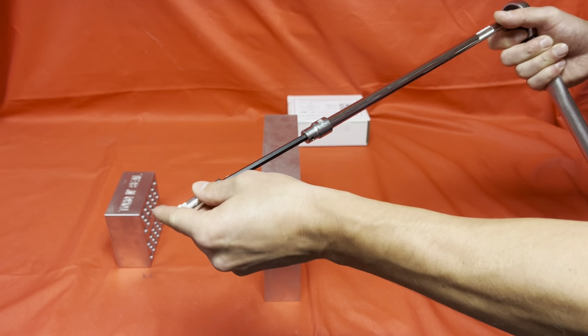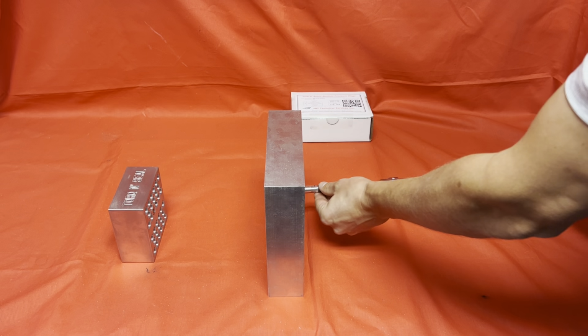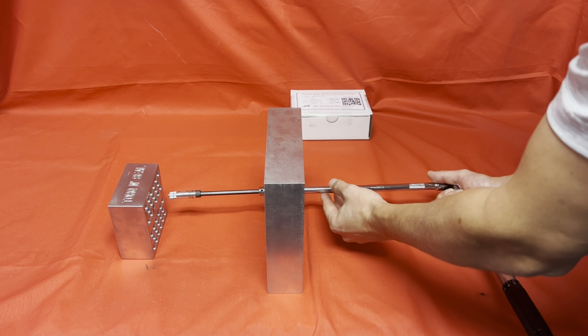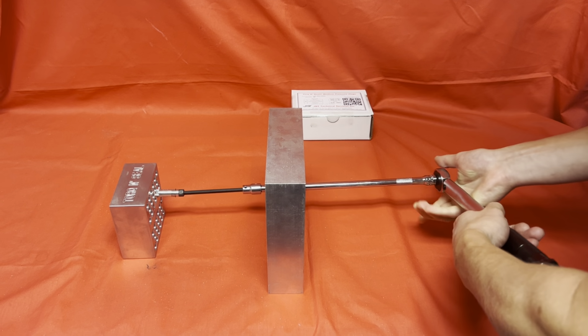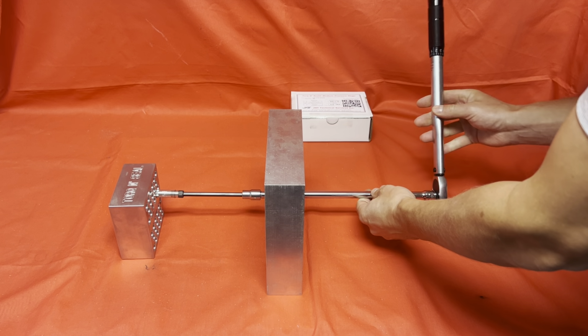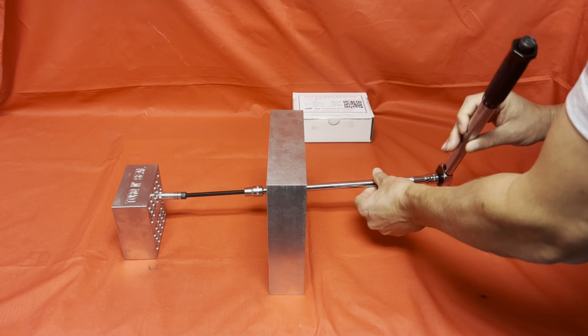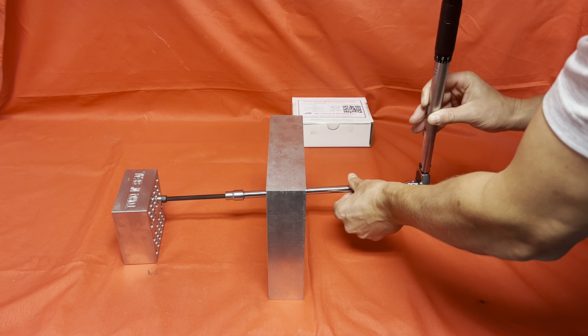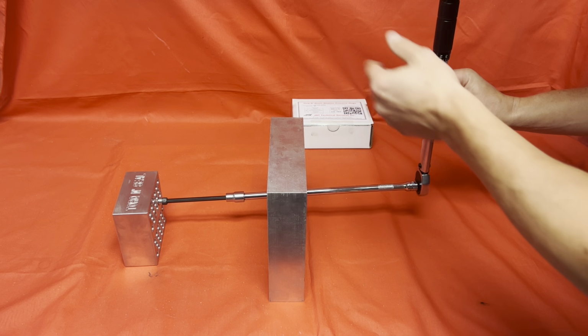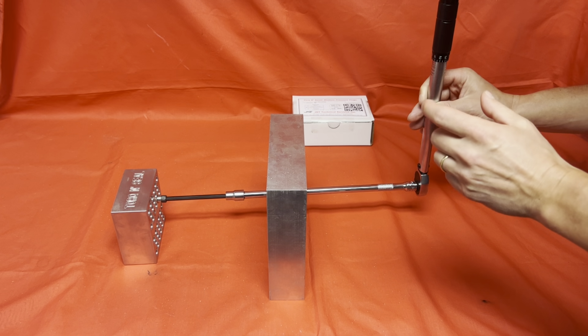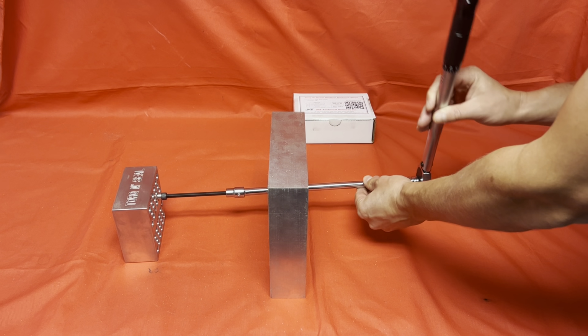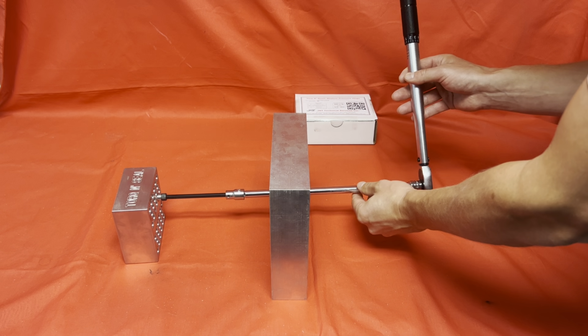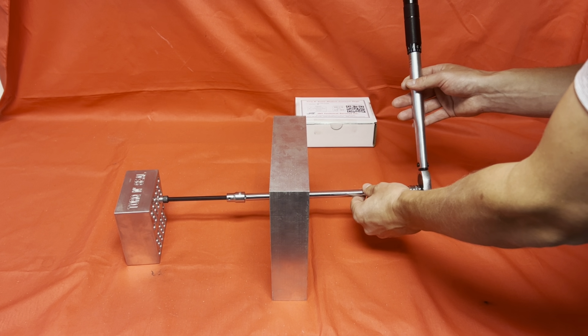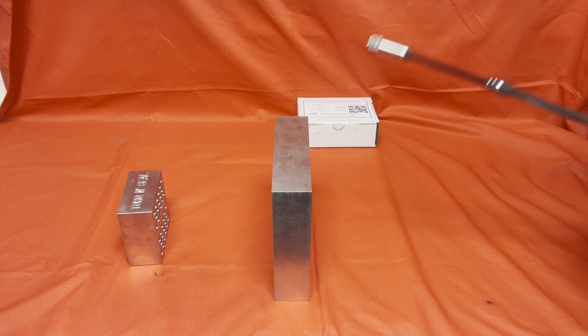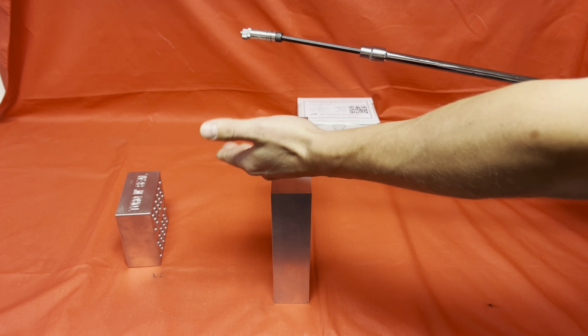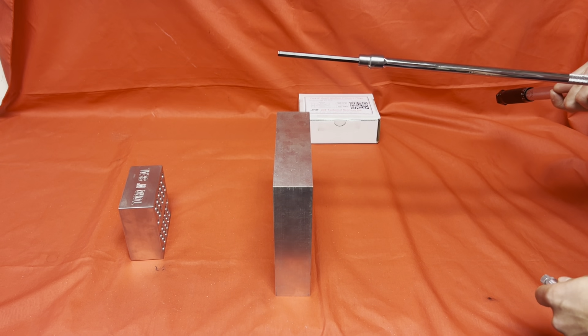I'm going to insert the plug onto here and then come through the water box and locate the plug. When you get there, you may have to give it a rotation in order to get that cam in line so the plug will slide into the tube. Now you can see that I pushed it in until the tube sheet ring butted up against that tube sheet face. And now I will simply torque the plug until the wrench clicks, and then I can simply pull free and be ready for the next one. Obviously the plug would stay installed in the tube once you'd reach the appropriate torque.